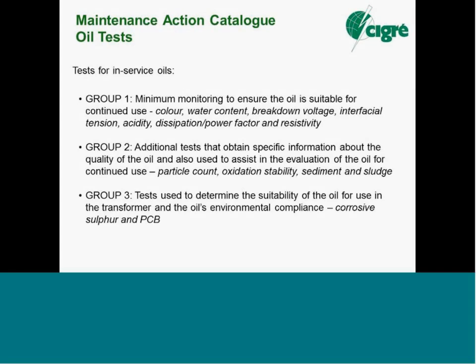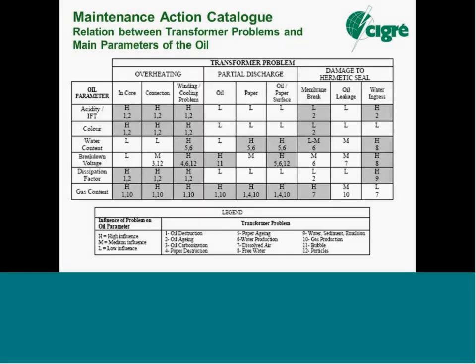In general, we have 3 groups of tests. Group 1 is probably the one you're more likely to experience or look at results for, to interpret in your work with power transformers. Groups 2 and 3 are more to do with selecting appropriate oils, or the condition of the oil with reclamation, or whether it's a particular inhibited oil or passivated oil, meaning its performance. And group 3, corrosive sulfur and PCB. That's usually because there's a contaminant or additive affecting the oil. So that's why they're grouped separately, group 3.